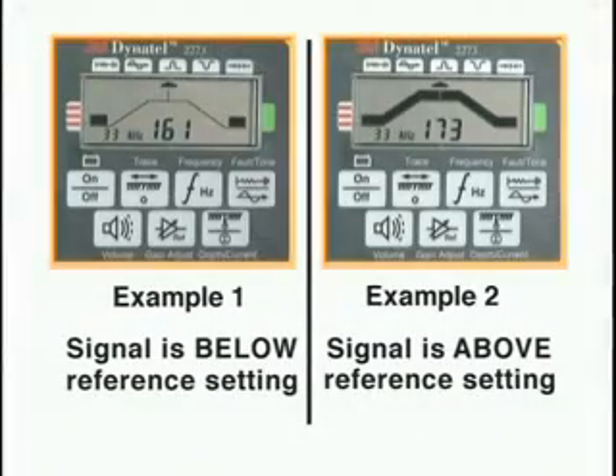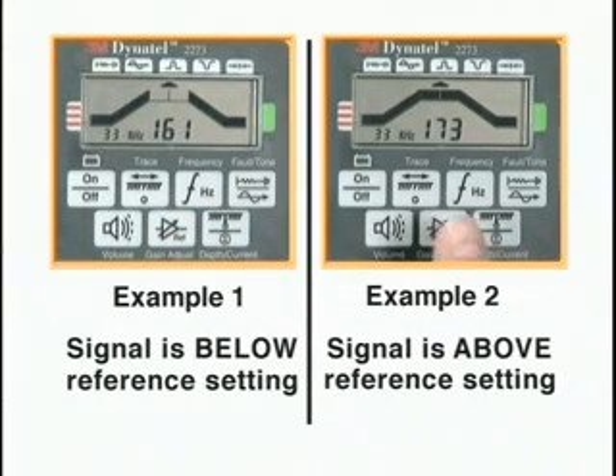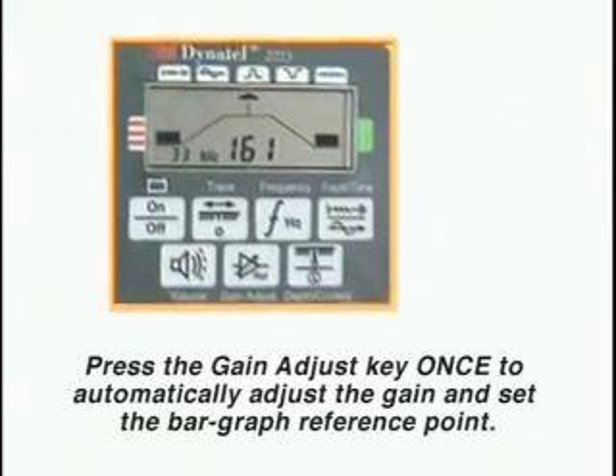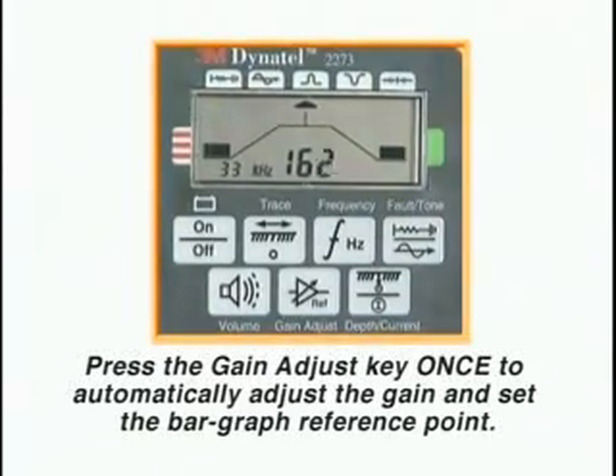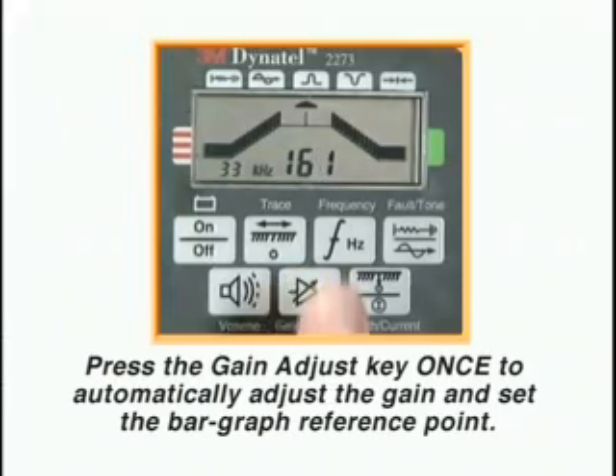The bar graph provides a visual indication of the relative signal strength being received by the locator from the cable being traced. Pressing the gain adjust key once sets the bar graph to the midpoint reference setting based on the strength of the signal being received by the locator at the moment the gain adjust key is pressed. Remember, you only need to press the gain adjust key once each time you wish to reset the bar graph level to the midpoint reference setting.